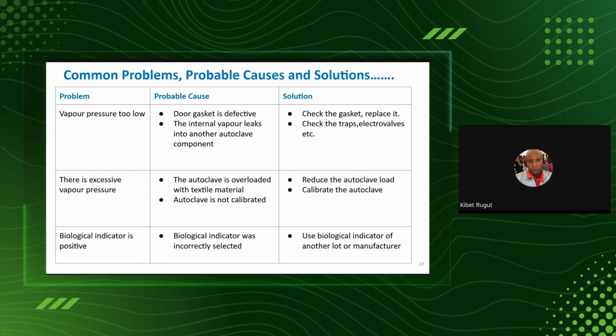Maybe another one that we come across is pressure that is too low. What can cause the loss of pressure? It is a defective door gasket, or internal vapor leaking into another autoclave component. We have pumps in the system, we have the exhausts and all that. You find that the vapor is going all the way to other chambers when it's not supposed to go there. So check the gaskets, check the valves, that is the solenoid valves, and then the steam trap that we have talked about.